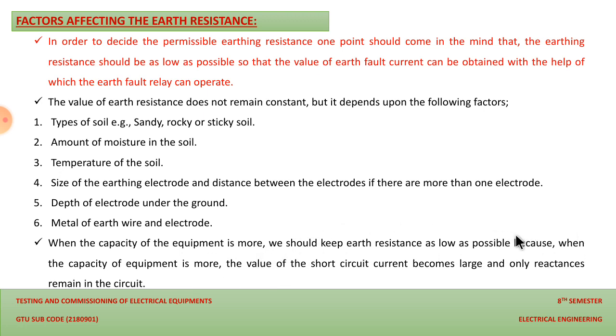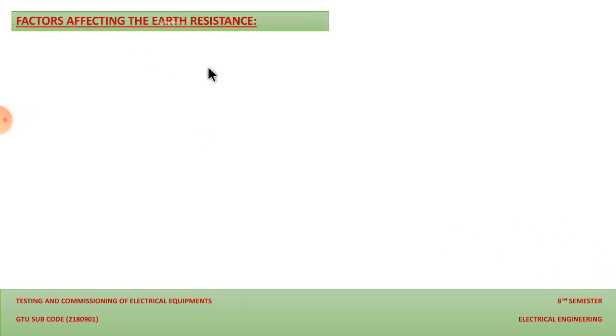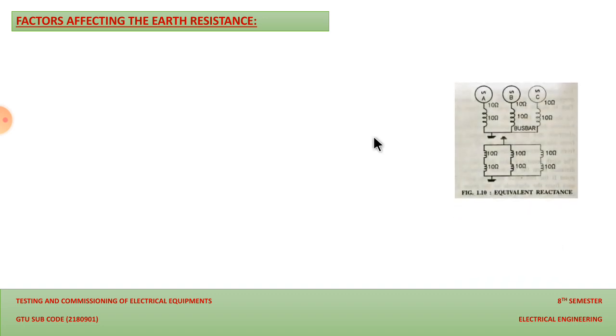So according to the level of short circuit current, we should provide a proper earthing scheme to the particular system, so that we can protect our system and the person who is working with the system from injury or any danger. Let us continue discussing the factors which are affecting the earth resistance. The major factor we have discussed is that if we keep the specific resistance, or earth resistance, as low as possible, then it will get eliminated and only the reactance will remain.